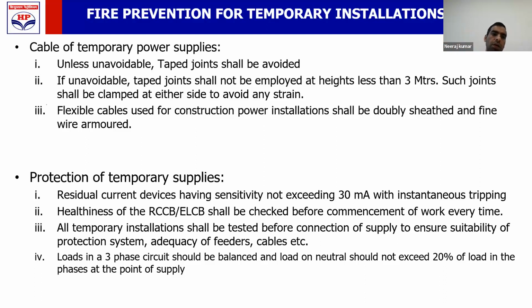Now we have talked about the incoming cable, now outgoing cables. These cables shall be without taped joints. In a refinery, we don't accept any kind of joint. We use cables without joints, even though this standard allows joints with certain provisions, which will be quite difficult to achieve. Tape joint, if unavoidable, shall not be employed at a height less than 3 meters.